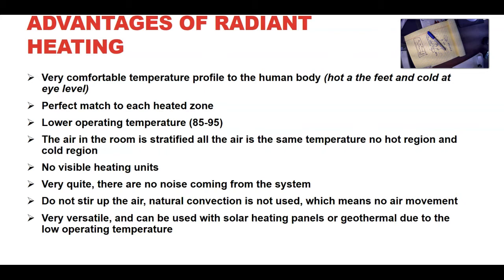Again, think about it. Steam uses above 210 degrees, the boiling temperature, to make steam, and hot water uses 180 degrees. And if you were to use radiant heating, you need water to be at 85 or 95 degrees. But it is, again, very slow acting.